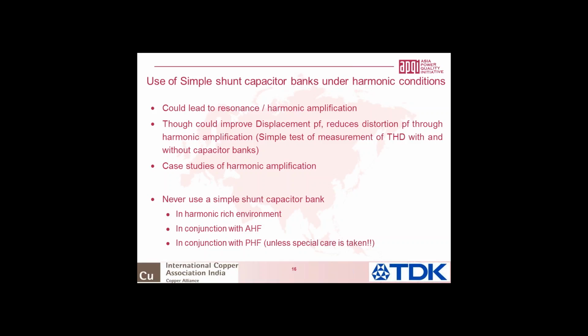I've seen THDs as much as about 20% coming down to 10% by just disconnecting the capacitor banks or adding an appropriate series reactor. You can go into a lot of details, but this is a very well-known concept. Never use a simple capacitor bank in a harmonic-rich environment, because you don't know what's going to resonate with what. There are too many inductances and capacitors on the network connected in series and parallel, and you could get into some kind of resonance.